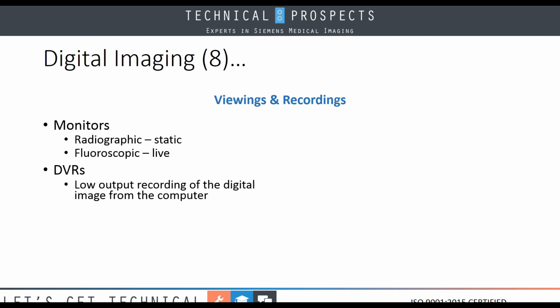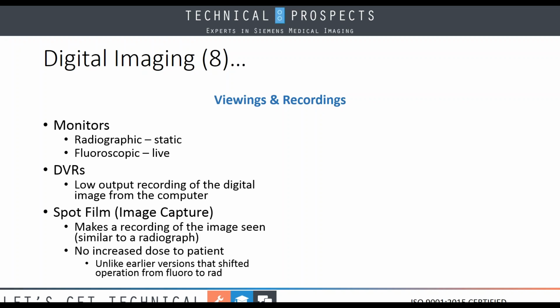DVRs replaced our VCRs. This is, again, a low output recording of the digital image from the computer. Spot film. This was the big change as far as what the digital world brought for us. If you think about your little camera phones or your portable digital cameras you have today, you can see what's going on, and when you press a button, it captures that image. We do the same thing here in spot film. The biggest change was no increased dose to the patient because we just captured that low-level fluoroscopic image, made an image capture, stored it off on the side for viewing later or printing on film or whatever they wanted to do with it. But again, this was the proof of what the radiologist saw during the exam.